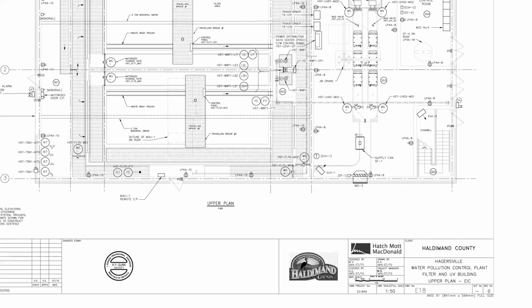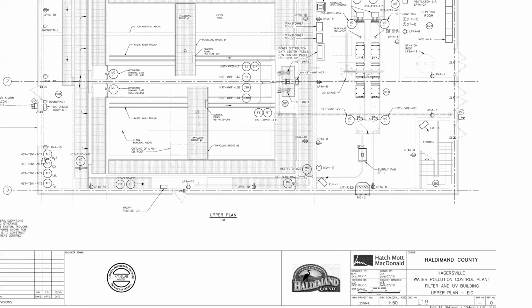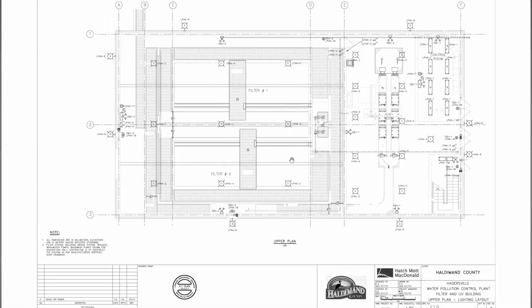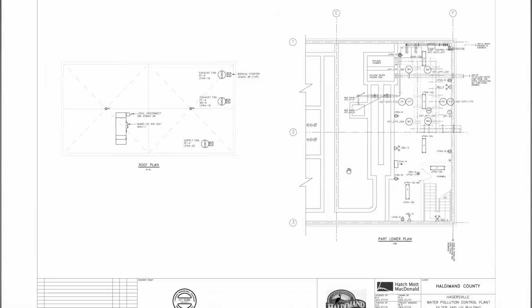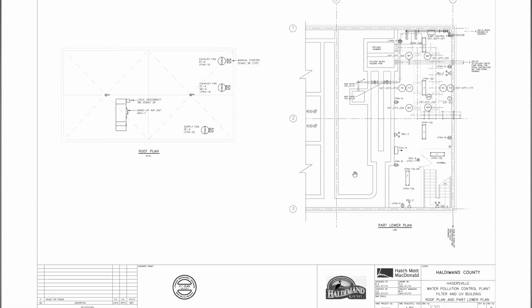What else? Over here, you've got gas analyzers. So AIT becomes a catch-all sometimes for some sort of analyzer. So this is an H2S, carbon monoxide, LEL, which is lower explosive limit, and O2. That's a very standard gas monitoring system. You'll see those in mining. You'll see those in oil and gas. You might add a couple of extra things for oil and gas. Very common for water, wastewater, anywhere where you're going to find lots of potential buildup of gases, or the lack of oxygen.